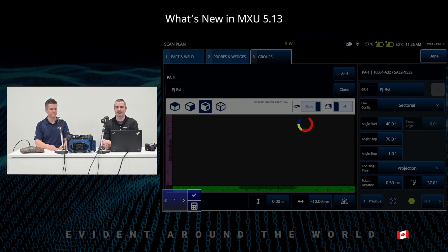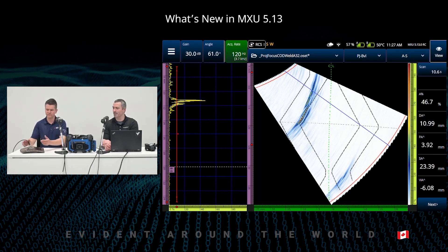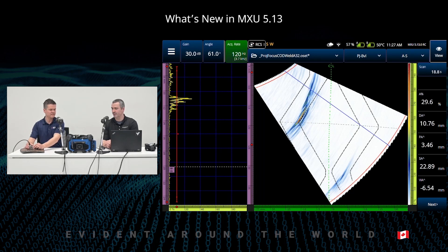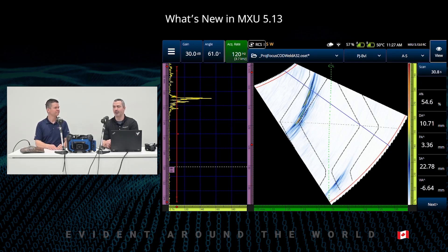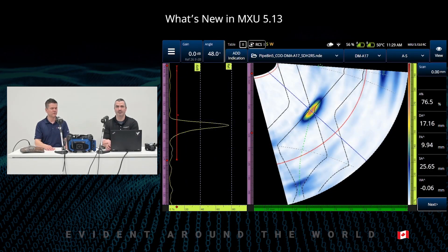This is a very powerful tool to achieve very good imaging. For example, if you want good crack sizing and the best definition possible, this coupon has a crack that developed during service. Because we're focused at the bevel of the weld, this happens to be a HAZ crack — a bit of a toe crack. We can see very clear definition thanks to projection focusing. That really enhances the definition of that crack. You also have an unfocused option for searching, also supported with COD. On top of that, we added support for COD with dual probes, covering dual linear probes and dual matrix arrays.